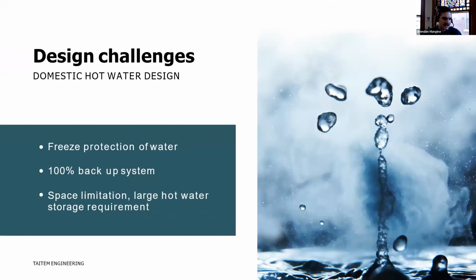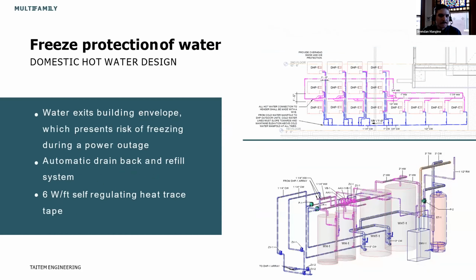So we ran into a couple of design challenges when initially designing this project. The first is that the water will exit the building envelope just because it can't be a split system. So we're actually sending the potable water outside the envelope, and that adds a big risk of freezing. The second one is that we wanted to add 100% backup to the system just in case something would happen to these heat pumps. And lastly, we ran into space limitations. Like I said, there's a lot of storage required for these projects, and we didn't have much space for our domestic hot water plant, and that's pretty typical for these projects.